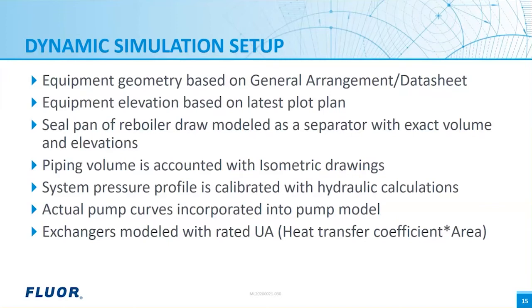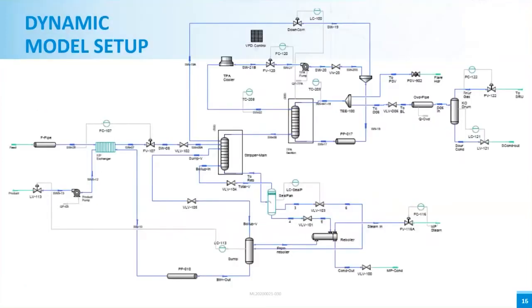The dynamic model was built in a simulator with all the listed detailed engineering information, and this is how a dynamic model looks in a simulator. A separate flash drum is used to mimic the sump pan for fluid drawn to the reboiler. This mimics the thermosyphon reboiler circulation hydraulics, and it is crucial to capture the hydraulic limitation during the upset with this detailed setup. You need to calibrate or validate your hydraulics with independent hydraulic calculations.